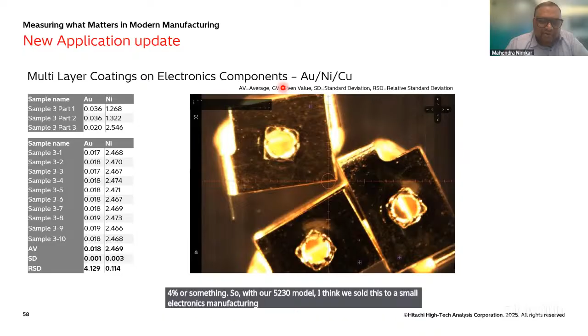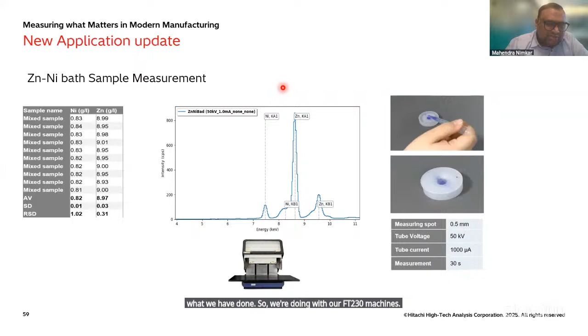Zinc nickel bath, I think this is not a new application, but if you see the RSD we are getting with the new instrument, in grams per liter, for example 830 ppm of nickel for the zinc nickel bath, what we have done. So we are doing this with our FT230 machines, and it is very encouraging. We have done the platinum bath solution, where we have gone up to the 25 ppm level with this machine. That is also a very good level we achieved with this instrument. Again, it is for precious element applications.